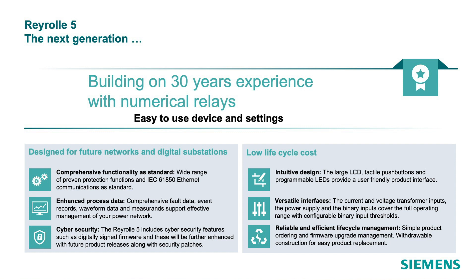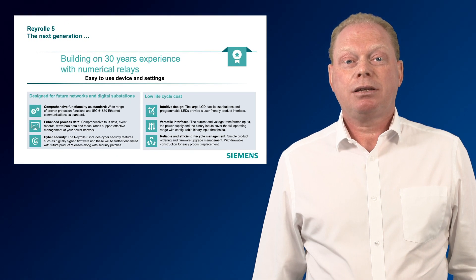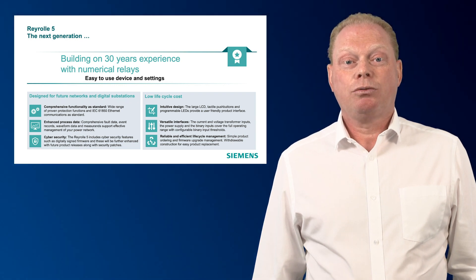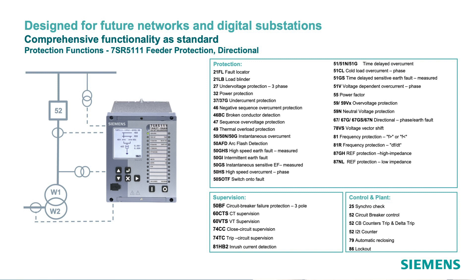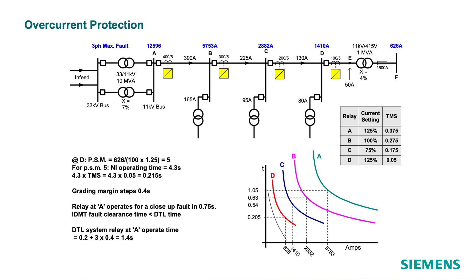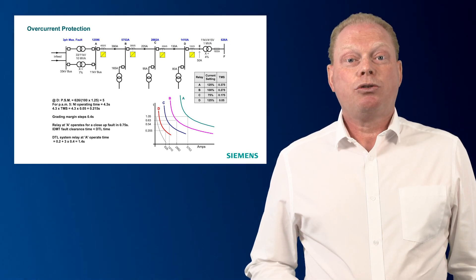The Reyrolle 5 is an ideal choice for distribution network protection and includes a proven range of protection functions to ensure reliability of operation. The current, voltage and binary inputs are configurable so are suitable for the majority of applications. The product includes an intuitive user-friendly interface, and this approach extends to the programmable tool Reydisp Manager 2. Reyrolle 5 provides models for both overcurrent and directional overcurrent protection with a wide range of functions that can be enabled where required. The main IDMT overcurrent element is used to protect the associated circuit and provide backup protection for downstream devices. The speed of operation is determined by the fault current level and can be used to grade with fuses on the LV system.